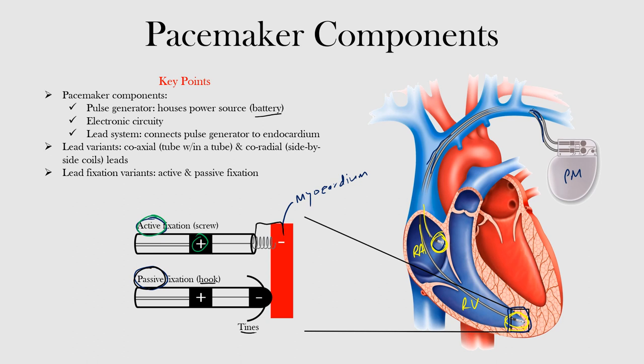Lead variants can be either coaxial — a tube within a tube — or co-radial, which are side-by-side coils. Lead fixation can be either active or passive. Active fixation inserts the lead into the myocardium for mechanical stability, while passive fixation uses tines like hooks to stabilize the lead against the endocardium.